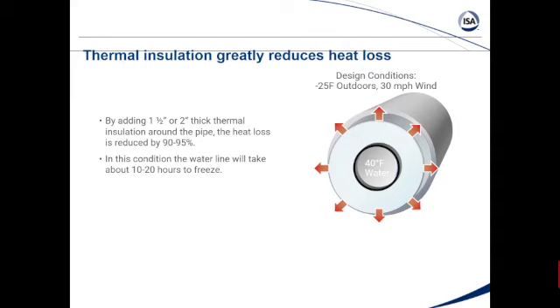I see that all the time. I've been on job sites when I was in the residential world, and they're like, oh, we're going to run these pipes on the exterior wall of the house. And I said, okay, well, what's going on there? Oh, we'll insulate it. It'll be okay. Actually, no, it won't. It won't be okay. It will buy you time, but it will not prevent it from freezing. It will basically reduce the amount of heat loss coming out of that pipe per linear foot, but that heat will still be lost eventually.